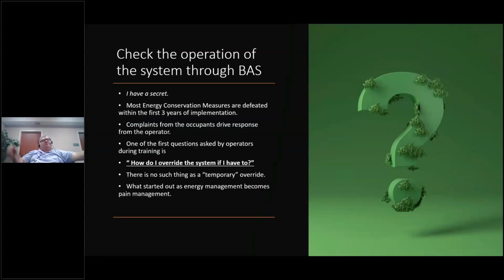I have a secret. This is controversial and it's actually been put in print, but this has been my experience: most energy conservation measures are defeated within the first 3 years of implementation. Complaints from the occupants drive a response from the operator. They're trying to solve the problem on their own because somebody's complaining about it. One of the first questions asked by operators during training is, how do I override the system if I have to? That is every job I've ever been on.